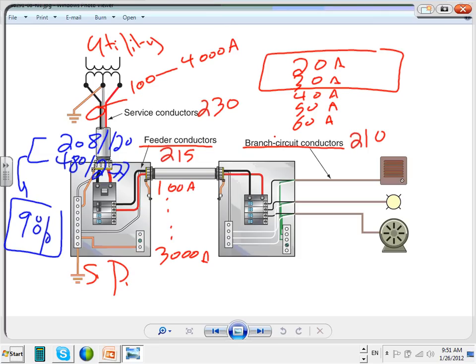Unlike in 80% of the world, where they use one voltage, 380, 220, and then you don't have a transformer. If you design in 80% of the world, you can have one voltage, and there's an advantage for that and a disadvantage, of course. But for us in the US, we almost use 480 because it's high voltage, good voltage.